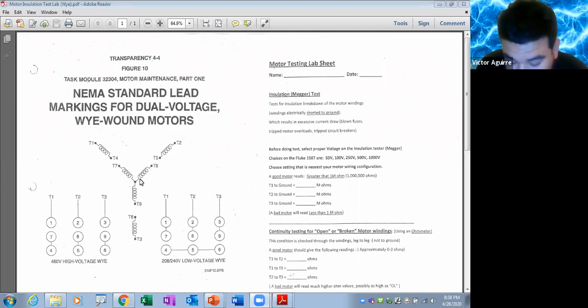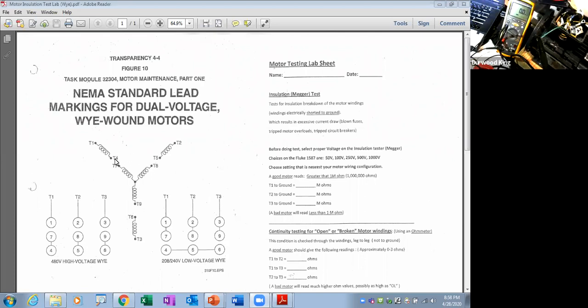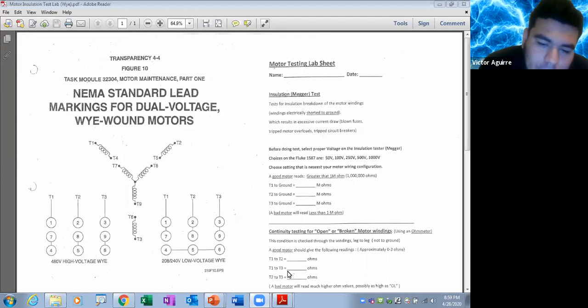Yeah. So the test that you're seeing, let's go ahead and do that. If we check through the motor, we should actually get a balanced resistance of ohms from 1 to 2, 1 to 3, and also 2 to 3. Okay, so let's try that on this one, and then let's try it on the good motor, and let's find out. Now, if you look closely over here on the lab sheet, what does it tell you, Victor, about the test here that you're talking about? At the bottom it says continuity testing for an open or a broken motor winding. You can use an ohm meter. You use an ohm meter for that. And you're going to check from T1 to T2, not the ground. Yep. And 1 to 3, and then 2 to 3.